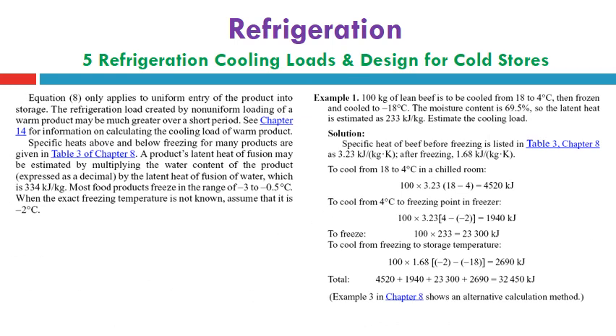Equation 8 only applies to uniform entry of the product into storage. The refrigeration load created by non-uniform loading of warm product may be much greater over the short period. See chapter 14 for information on calculating the cooling load of warm products.